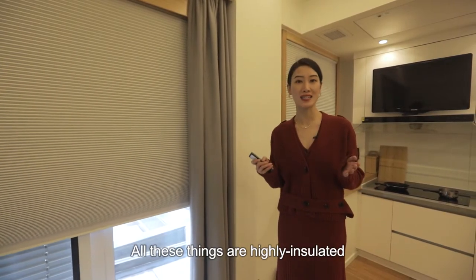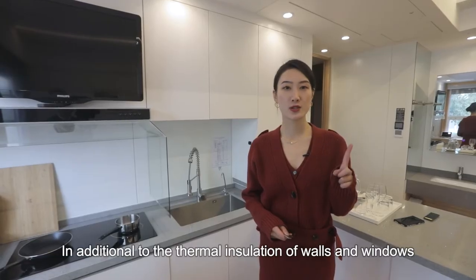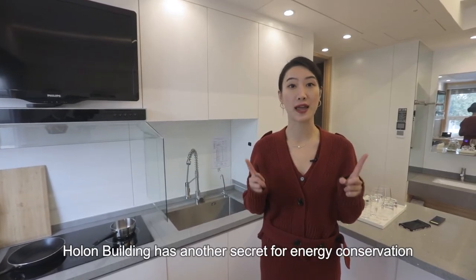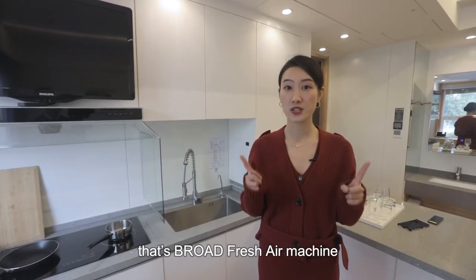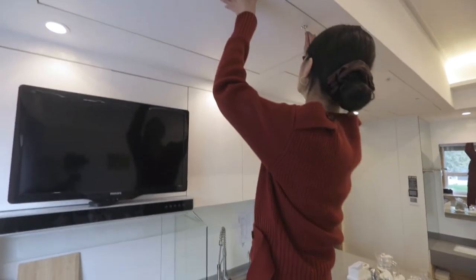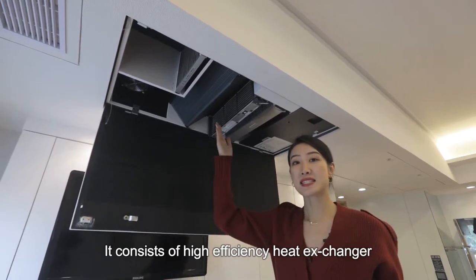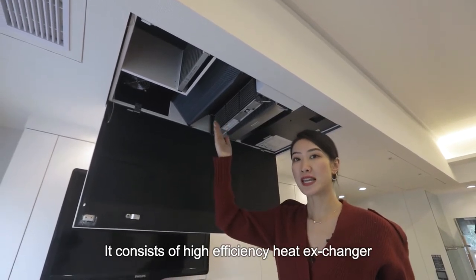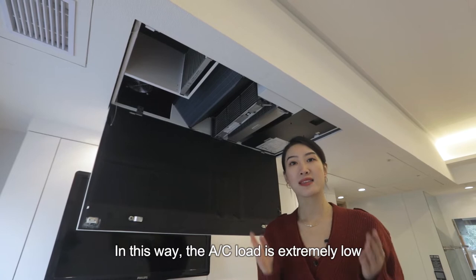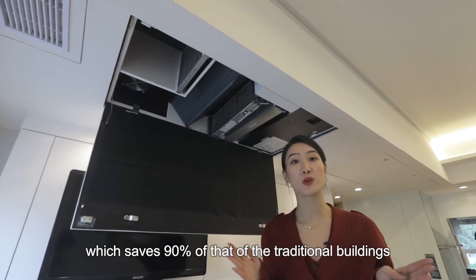All these things are highly heat insulated and the room is kept warm in this way. In addition to the thermal insulation of walls and windows, the Holon Building has another secret for energy conservation — that is the fresh air machine. Let's open it to see the inside. It consists of a high-efficiency heat exchanger which recovers 80% of exhaust heat. In this way, the AC load is extremely low, which saves 90% of that of traditional buildings.